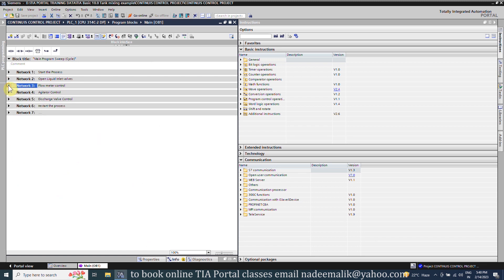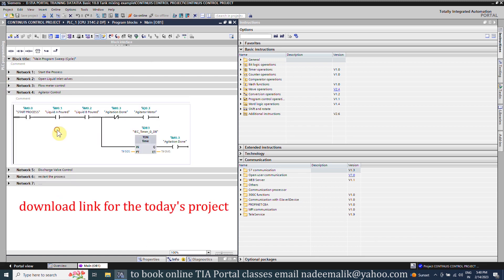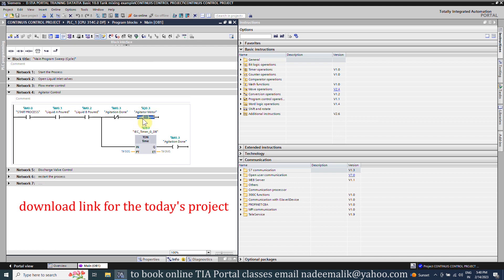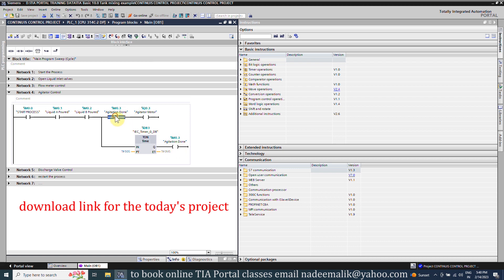Next in network number four we have a logic to control the agitator. When both liquids A and B are poured in the tank these bits will close and start the agitator motor Q0.3. In parallel the timer also starts with 50 seconds preset time. Once 50 seconds are over the timer will turn on the agitation done bit M0.3, and this same bit will turn off the agitator motor Q0.3.